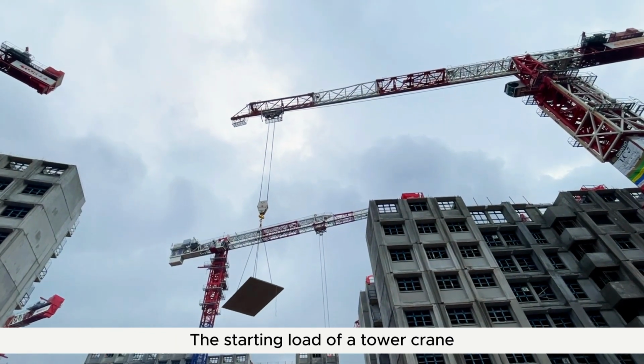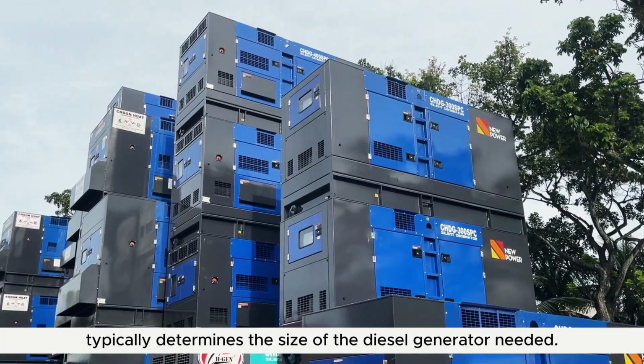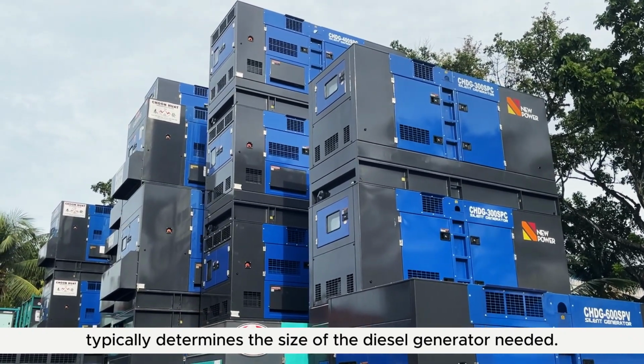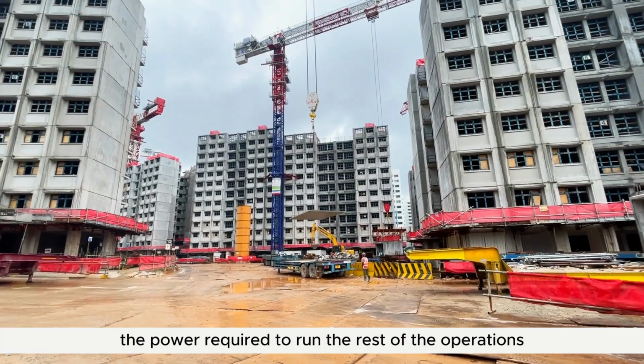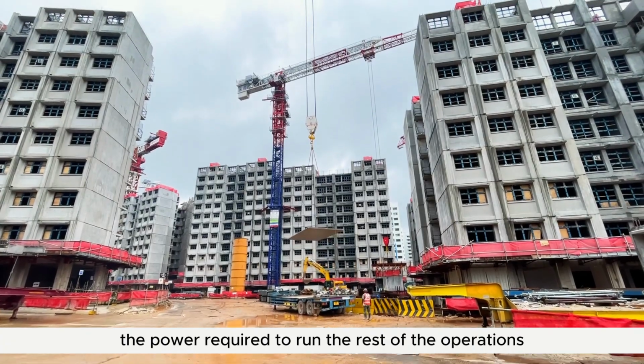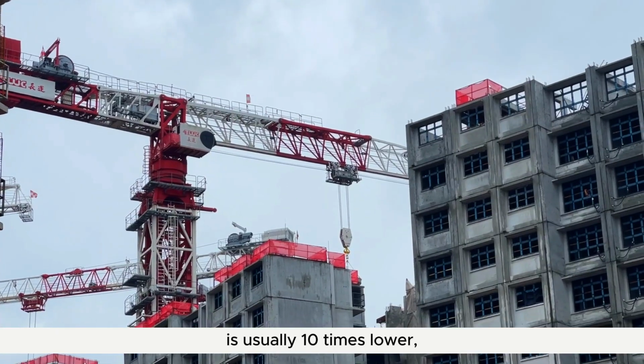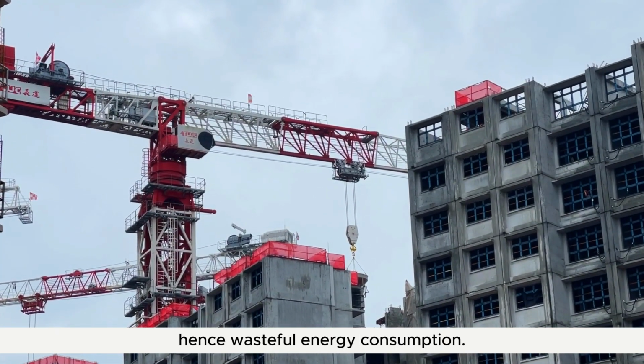The starting load of a tower crane typically determines the size of the diesel generator needed. However, the power required to run the rest of the operations is usually 10 times lower, hence wasteful energy consumption.